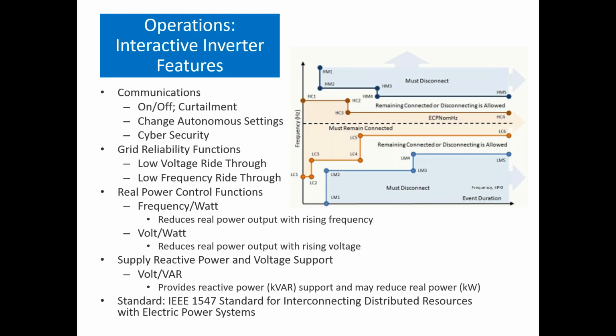Examples of settings that it might want to reach out and control include low voltage ride through and low frequency ride through. It might call upon the inverter to source reactive power. And so the diagram on the right here shows the IEEE approach of opening up the envelope between what the inverter can do, which is in the orange there, what it must do, which is the blue there, and then this white area in between, which can be informed by interactive communications with the utility. So that's standard IEEE 1547, which is being referred to there.